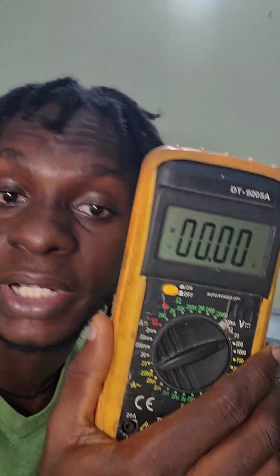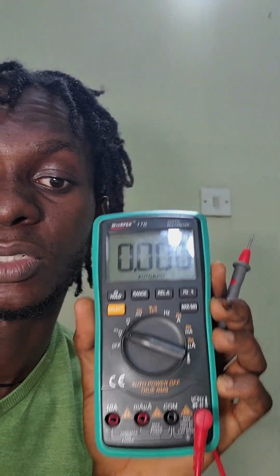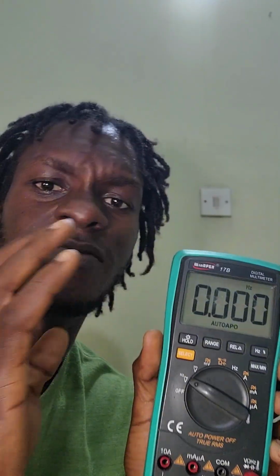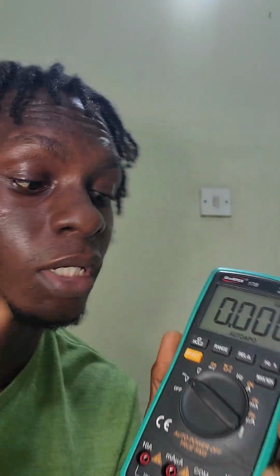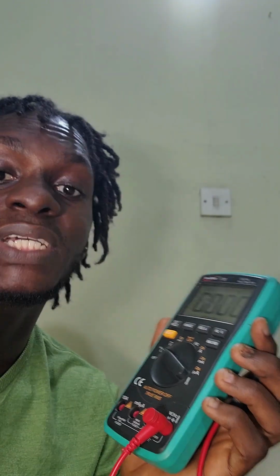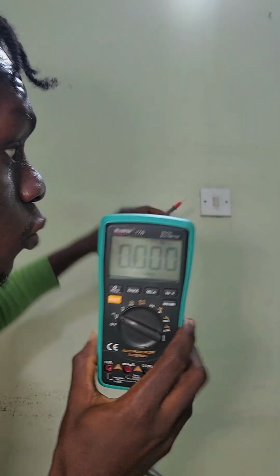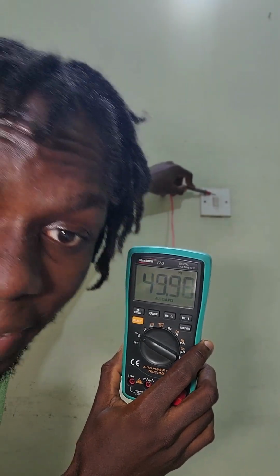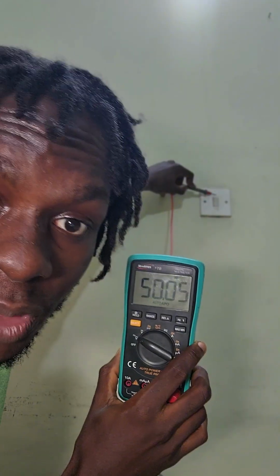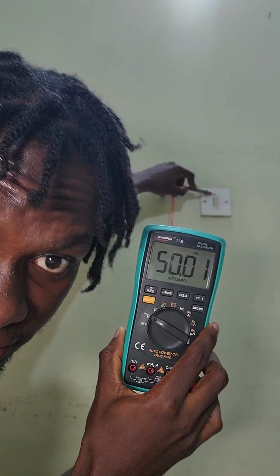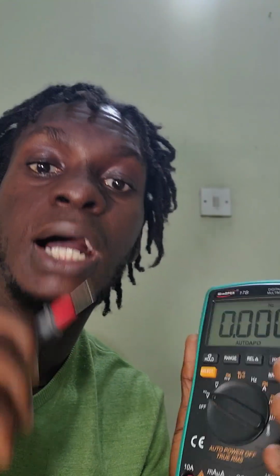This is one of the meters you cannot find on manual range digital multimeters. You can only get them on this type of meter and other ones even more sophisticated than this particular one. The frequency meter picks the frequency of the AC current even before it touches anything. That's why I'm able to read the frequency of the power passing through this switch without opening it. As you can see, I'm reading 50 Hz here. One of the most beautiful things about this frequency meter is it also has a duty cycle meter. Let me explain, but first let me show you how the frequency meter works.